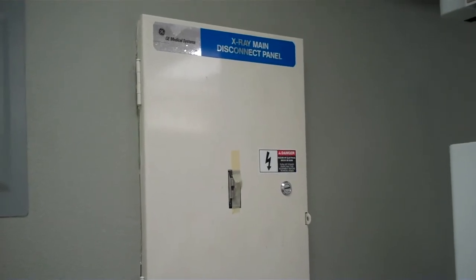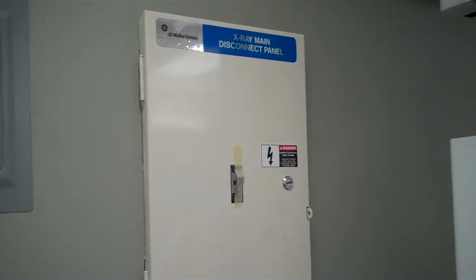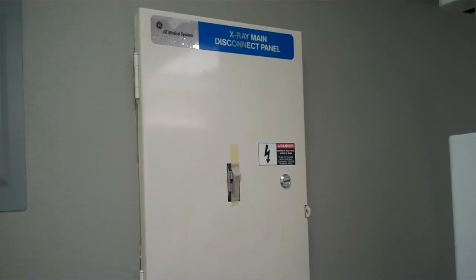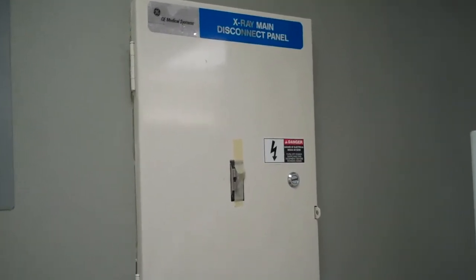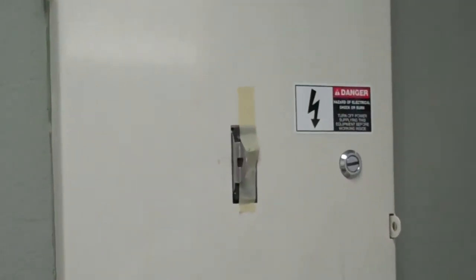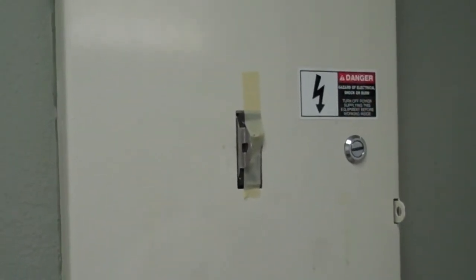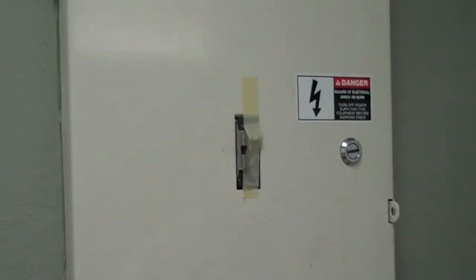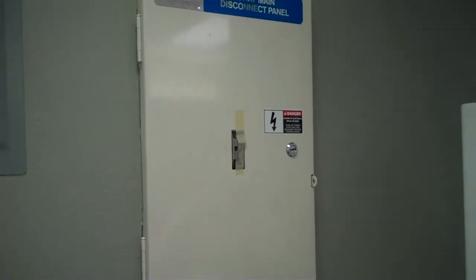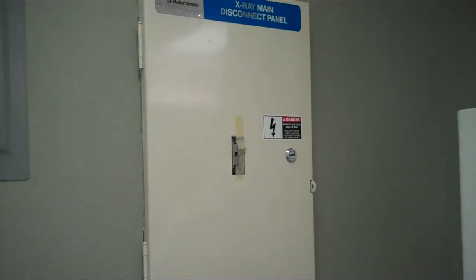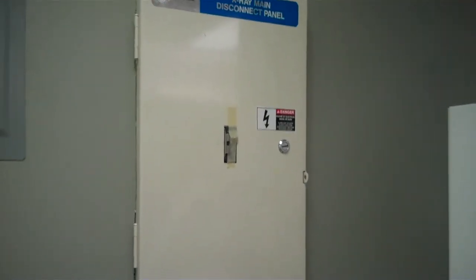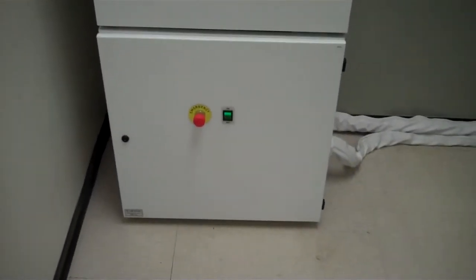In room B, the first thing we look at is the main X-ray circuit panel. You'll notice that there is tape over the circuit breaker in the on position. This is not to be turned off and is not the first step in turning the room on, since it is already activated. The first step in turning the room on is to turn the generator on.